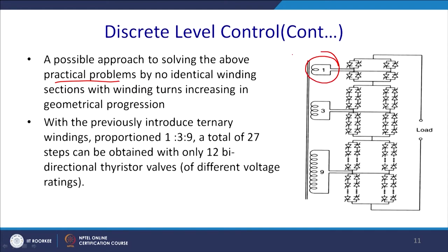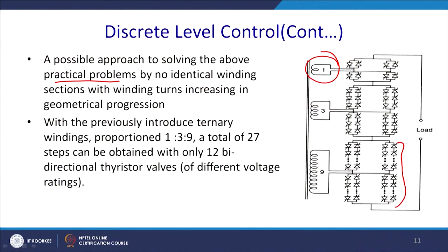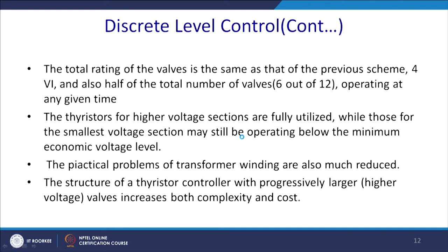So, it has one turn, or the ratio is 1, 3 and 9, and subsequently the thyristor ratings will change. So, with the previously introduced ternary winding, in the proportion 1 is to 3 is to 9, a total of 27 steps is obtained with only 12 bidirectional thyristor valves of different voltage ratings. So, this kind of configuration may solve the previously discussed problem. The total rating of the valve is the same as that of the previous scheme, 4 VI, and half of the total number of valves, so 6 out of 12, are operating at a given time, thus reducing the conduction losses also.